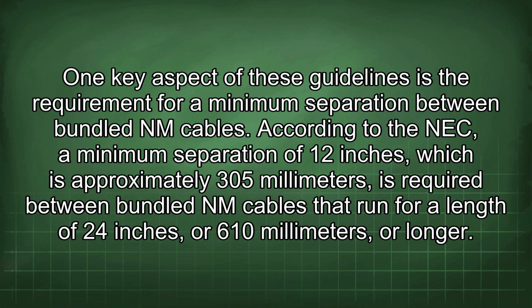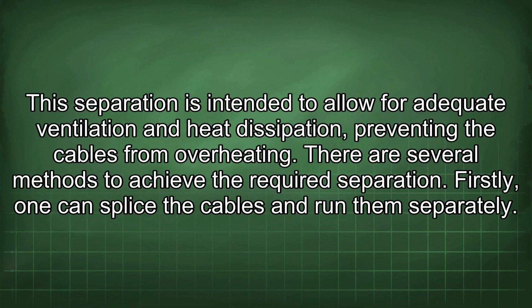One key aspect of these guidelines is the requirement for a minimum separation between bundled NM cables. According to the NEC, a minimum separation of 12 inches, which is approximately 305 millimeters, is required between bundled NM cables that run for a length of 24 inches, or 610 millimeters, or longer. This separation is intended to allow for adequate ventilation and heat dissipation, preventing the cables from overheating.